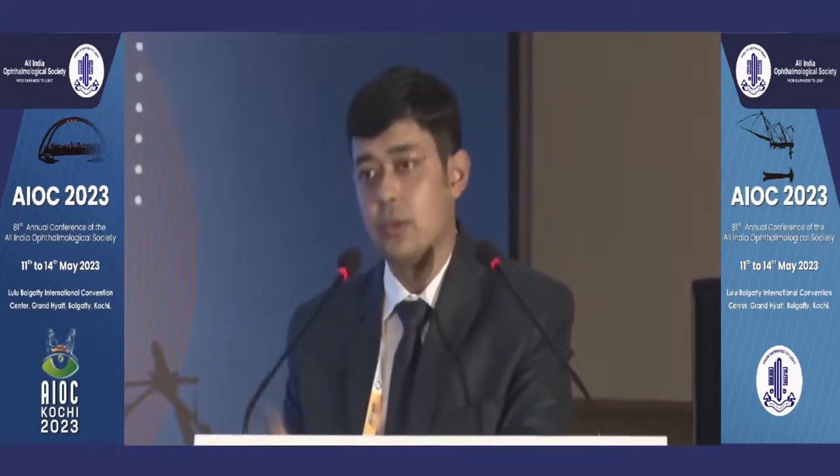And in case you're using that, do you have any suggestion as to what A constant they should be using, whether it's an acoustic A constant or an immersion A constant or an optical A constant? Yeah, they should be using the acoustic A constant. That's what I mentioned, that both the acoustic A constant and the fact that you're using the ultrasound, there is an option for you to use the acoustic A constants in the calculators, and that needs to be entered when you're using your immersion device.